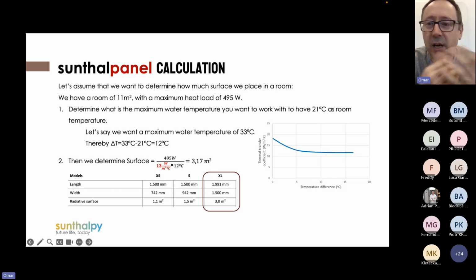How do we calculate the surface that we have to put on a specific room? I told you before, we need 30% of the surface of a radiant floor to be equivalent. So basically, if you just cover 30% of the building, you would operate this system in the same conditions as a traditional radiant underfloor heating system, and it will be much better for cooling. But if you want to make a good calculation, and for example, instead of just the same performance as a traditional radiant floor system, you want to be even better and work with lower temperatures, you have to make the following calculation.